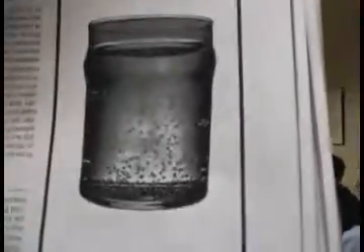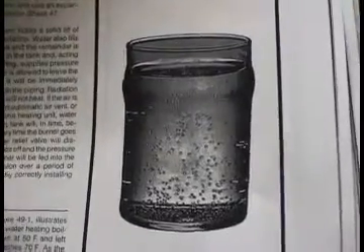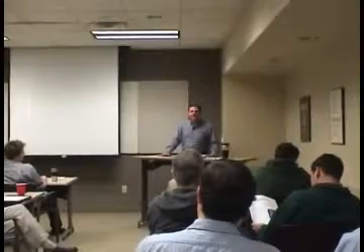Most forced flow hot water heating systems are closed to the atmosphere and use a compression tank to handle the expansion of the water. That's something I didn't go over in the gravity feed: not only does the specific weight change, but water expands when it's heated and contracts when it's cooled. So you need to have an expansion tank in your hot water system. You need to make sure that tank level is somewhere in the mid-range, not full, not empty.